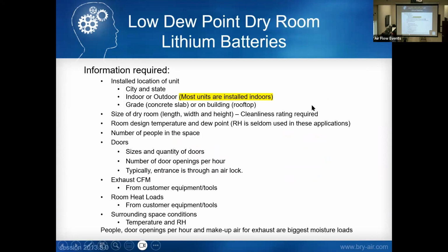And probably the newest market that has really picked up, especially in the last 2 years, is lithium battery manufacturing for automotive electric vehicles. I have to say our business doubled last year just because of this market predominantly. It's been a big market. Basically, in the facilities where they manufacture these lithium batteries for automotive, they need to be at a -40 dew point typically in that space. So you have to have dehumidification. It's very critical to get to that low dew point because any moisture in those rooms will cause problems with the manufacturing process of the batteries.